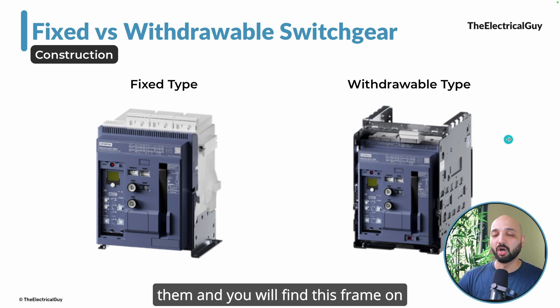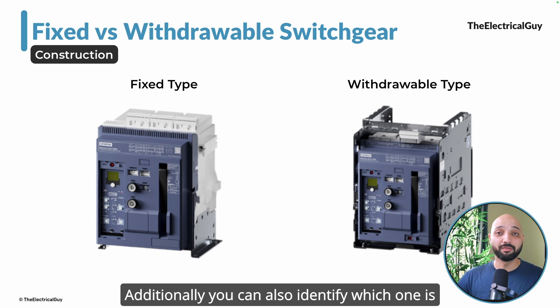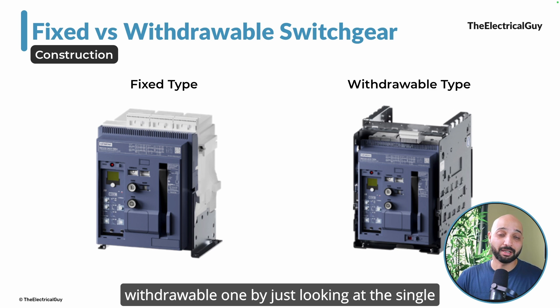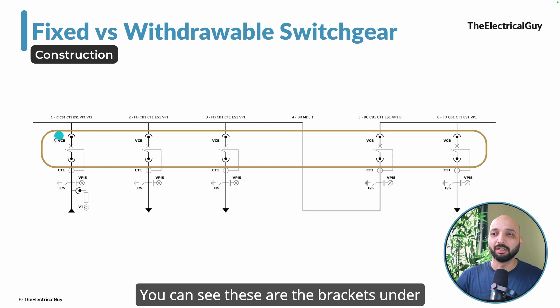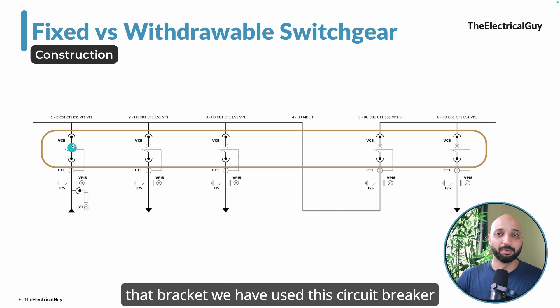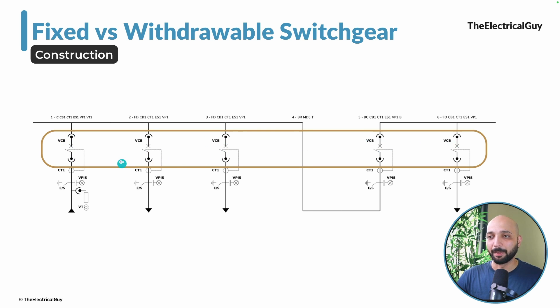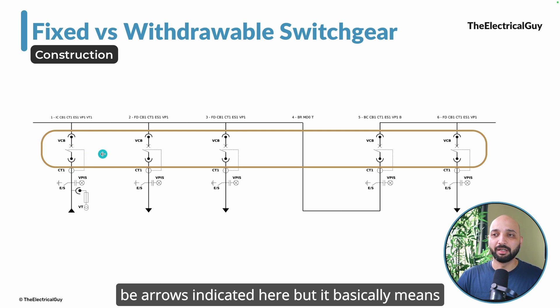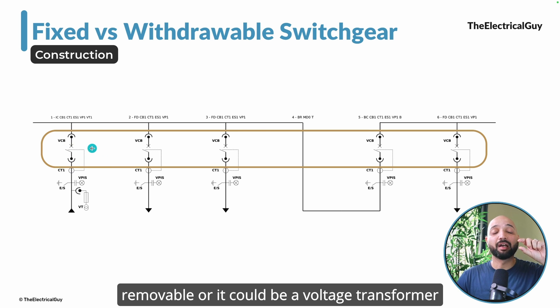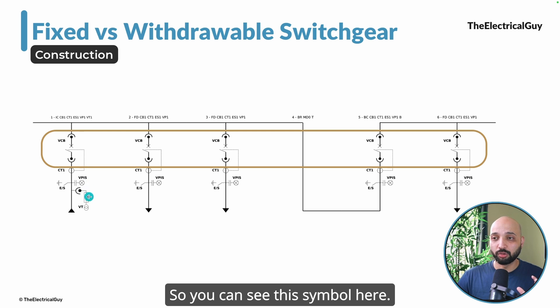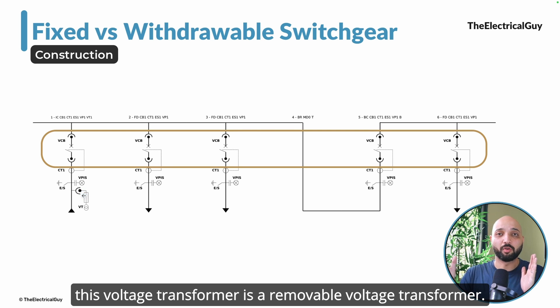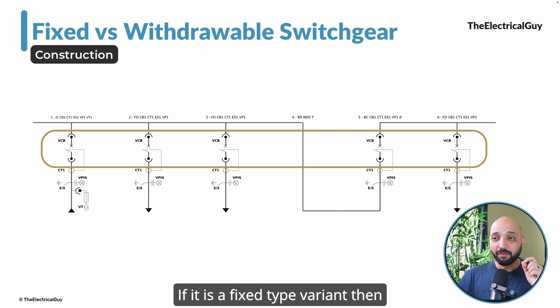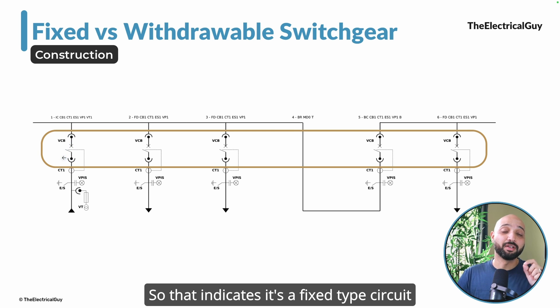If you get a chance to see those breakers, you will find this frame on the withdrawable type circuit breaker. You can also identify them on the single-line diagram — the single-line diagram differentiates fixed and withdrawable type by using brackets. Under that bracket you will see the circuit breaker symbol, or there may be arrows indicating the same thing — meaning those breakers are removable. For a voltage transformer, a bracket means it is a removable VT. If it is a fixed type, there are no brackets or arrows — just a direct connection.